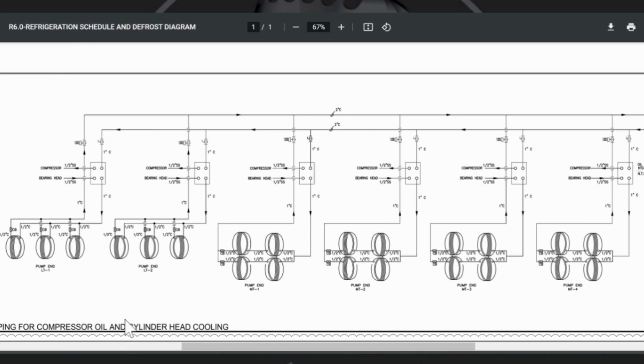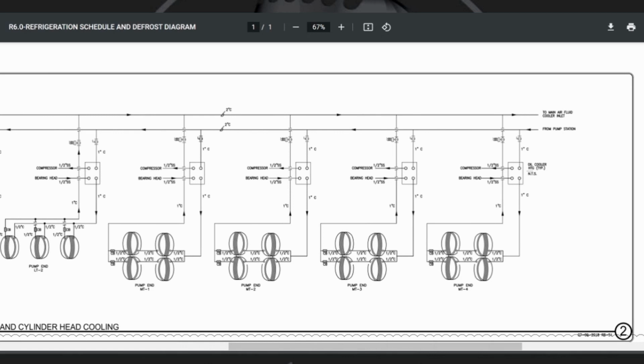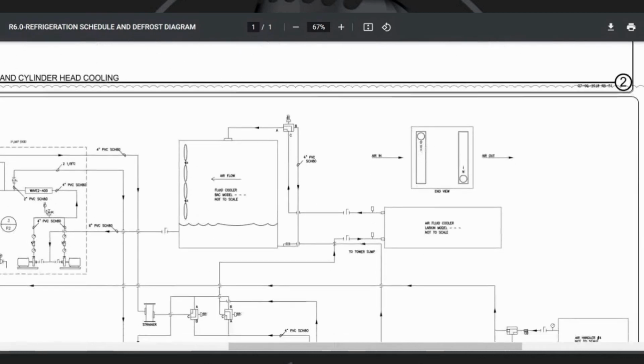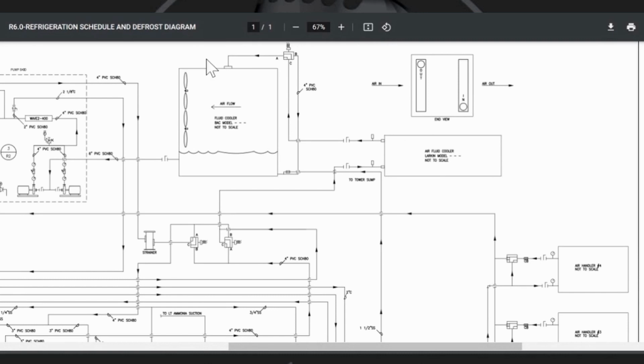And that's to make sure that we get even flow across the heads. Yes. And those are the ones that are basically getting you the 10 GPM that we were talking about before. Yes. So the temperature of the water coming in, typically averaging about what there, Ed? It's condenser water at 78 degrees. Okay. All right. And then so 78 degrees, when I was looking at the refrigeration schedule, basically the TD on these is about 10 degrees if I'm not mistaken. Is that right? The system is designed on the condensing side for a 10-degree TD. Mm-hmm. But one of the things we learned, Rayleigh's has the ability to measure in real time our evaporator load.